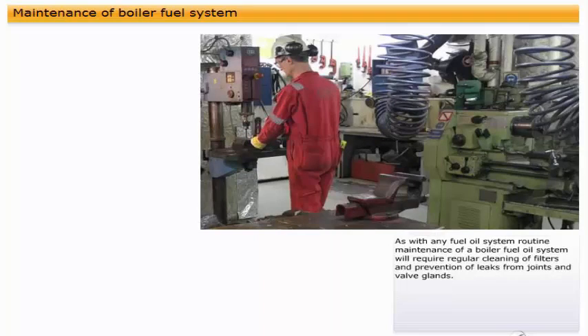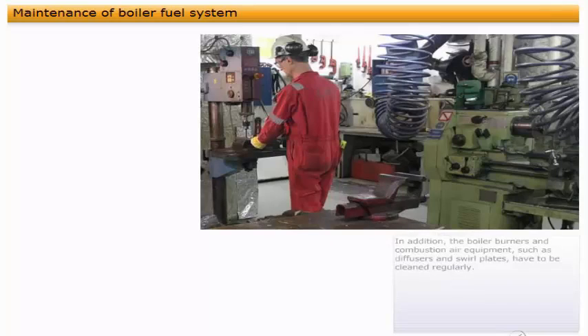As with any fuel oil system, routine maintenance of a boiler fuel oil system will require regular cleaning of filters and prevention of leaks from joints and valve glands. In addition, the boiler burners and combustion air equipment, such as diffusers and swirl plates, have to be cleaned regularly.